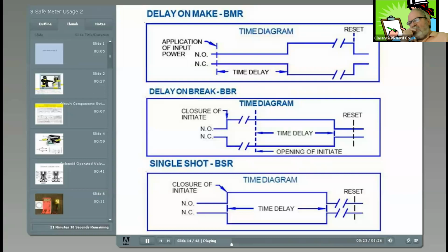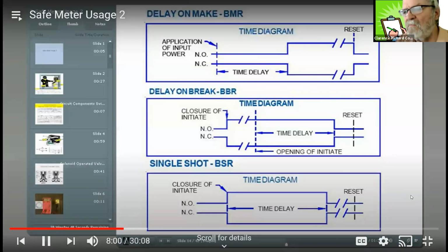Delay on break, BBR. Power must be applied to the input at all times prior to and during timing. Upon closure of the initiate switch, the output contacts transfer and remain transferred if no further action is taken. When the initiate switch is opened, the time delay begins. At the end of the pre-selected delay period, the output contacts revert to their original position.